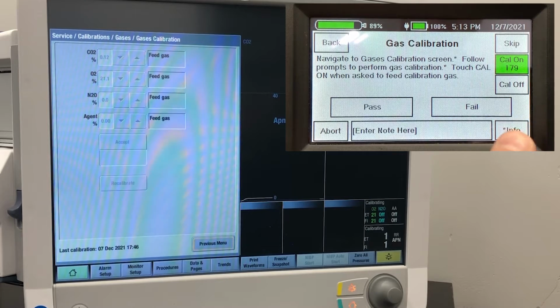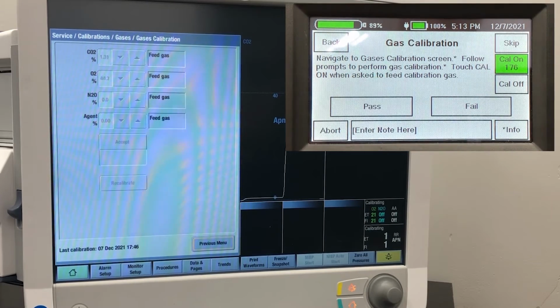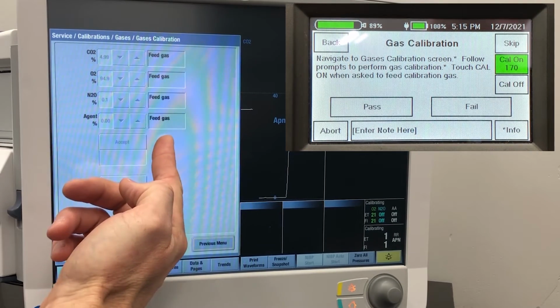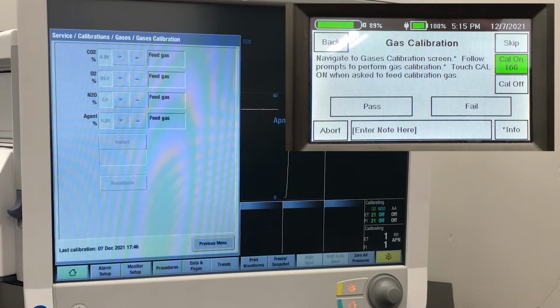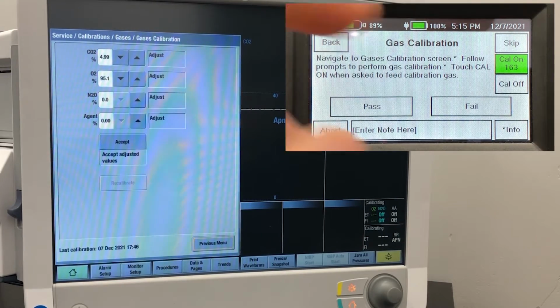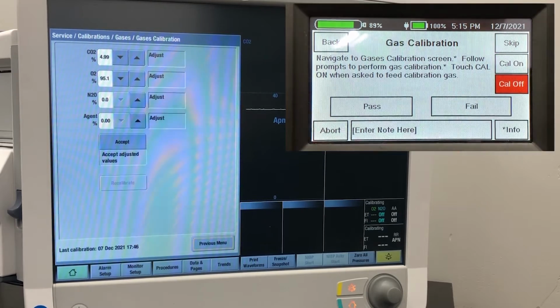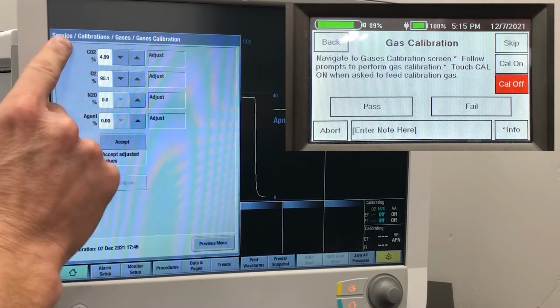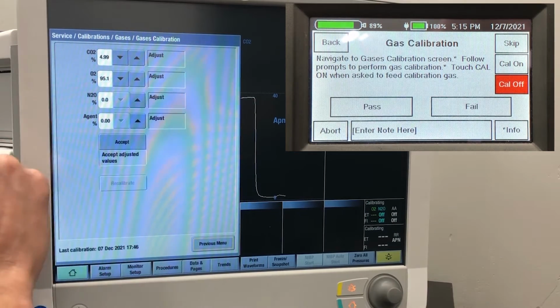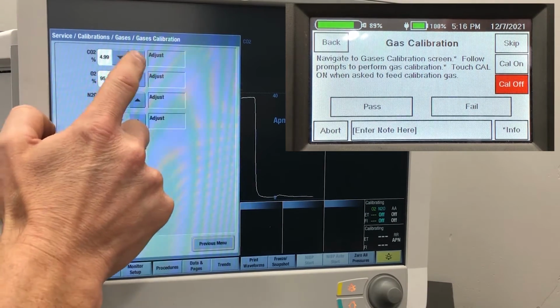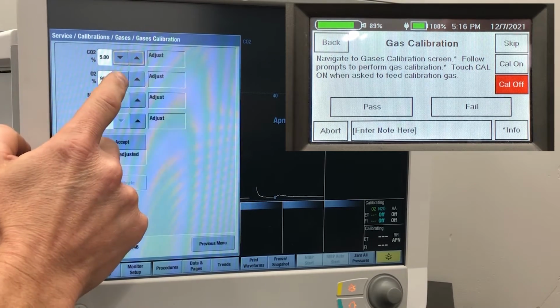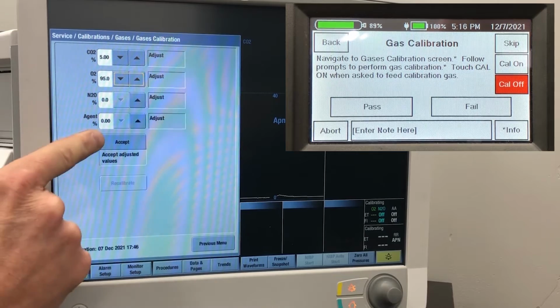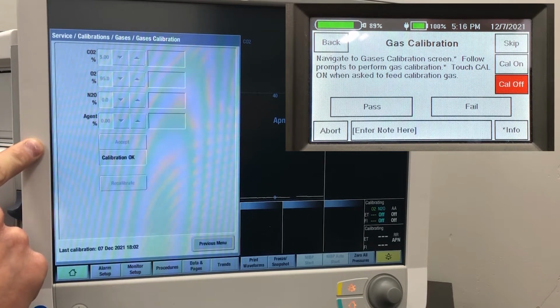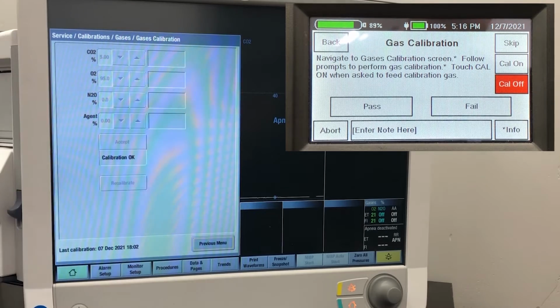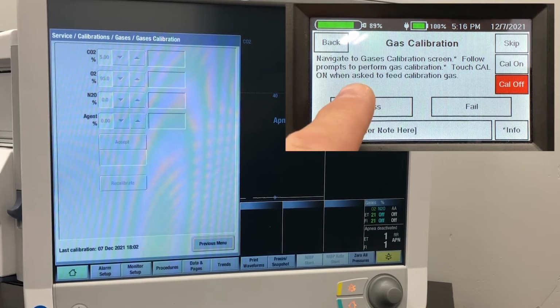That causes the SmartTank to deliver calibration gas at a controlled flow that conserves the calibration gas. We wait until the monitor says adjust, which means it's done making the measurement, and we can turn off the calibration gas to conserve calibration gas. So now it's saying adjust. We adjust these values to read what the calibration gas mixture is. So this is a 5% CO2 mixture, balance oxygen, which is 95% oxygen. And we touch accept. When the monitor says calibration okay, it means that it's accepted the calibration, and we can touch pass on the SmartTank.